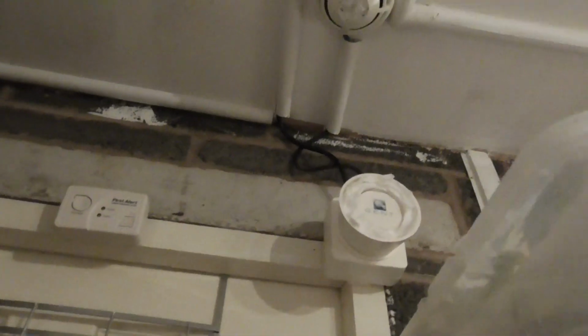So I'm going to start with the old style call point. We need this key. It's quite fiddly to do this call point, but hopefully I can activate it. So it goes in the corner over here, and then see if we can push this up, and just push up. There we go, so that works. Now we can just push the key back out. It's a bit fiddly to do, there we go. And then reset it. So there we go.